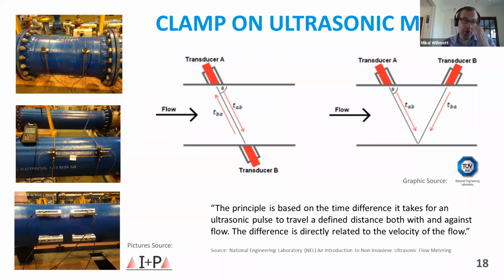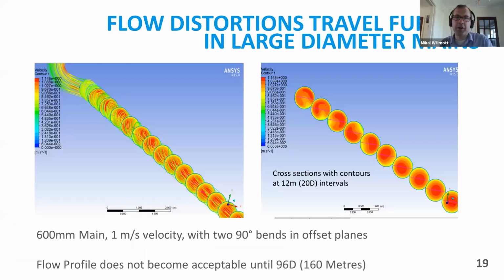So on the left-hand side picture, you've got one transducer sending a signal to the other transducer, and they take turns in sending and receiving signals. On the right-hand side is what's probably more popular in the water industry, where you'll see a V formation. You have two transducers on the same pipe wall, and they send signals and reflect them off the far pipe wall. Okay, so that's just a really basic introduction to electromagnetic meters and clamp-on ultrasonic meters.